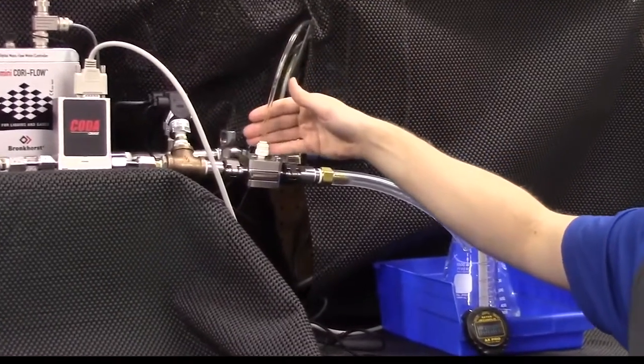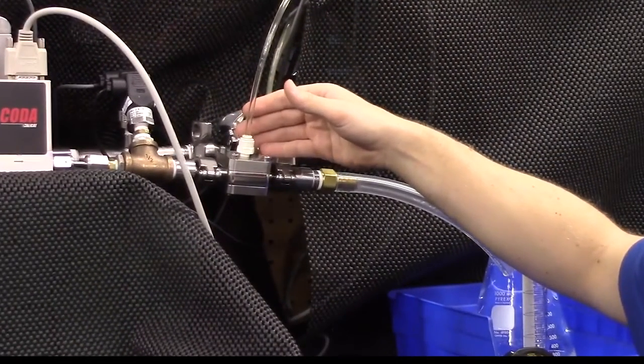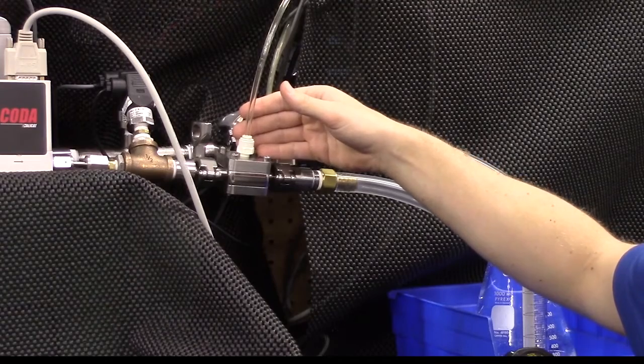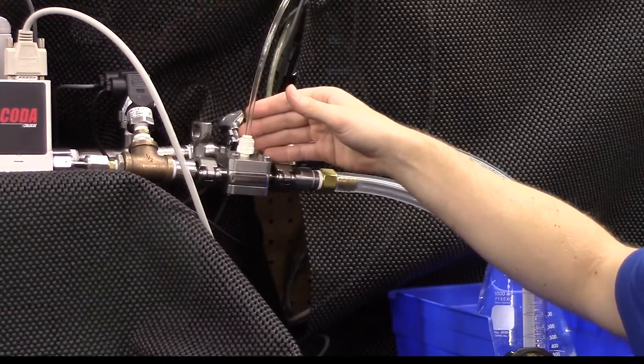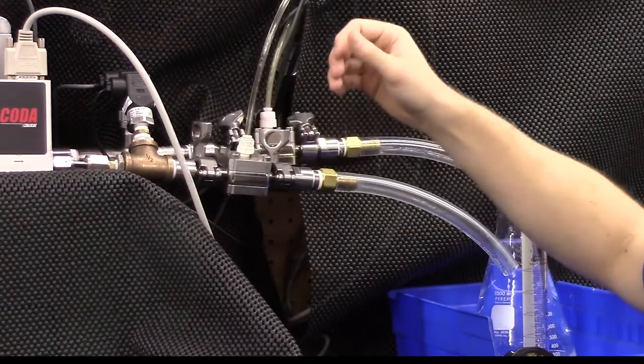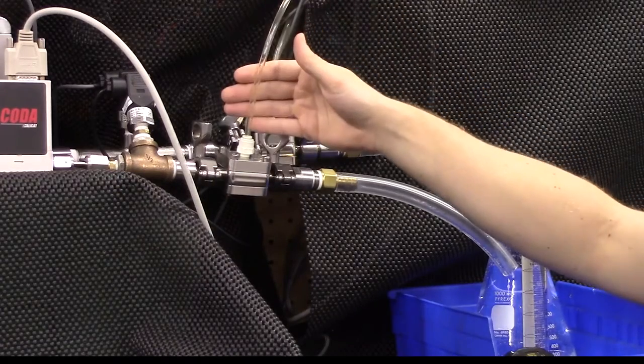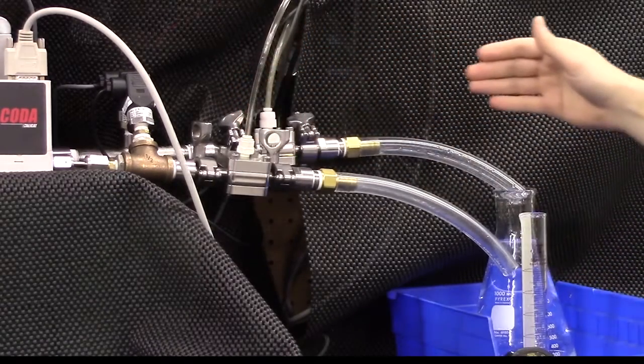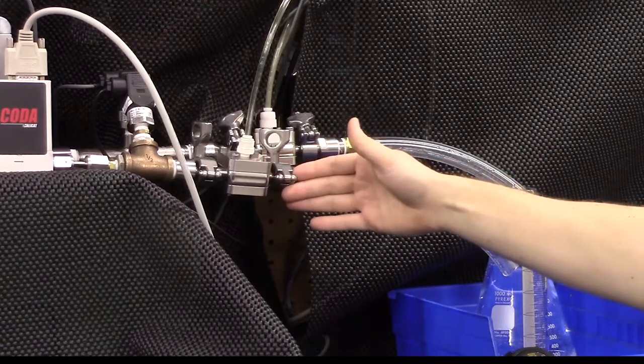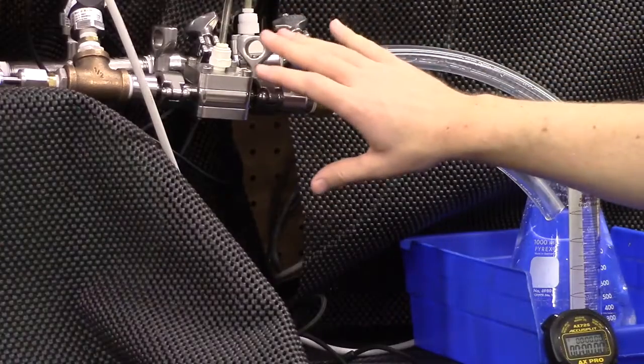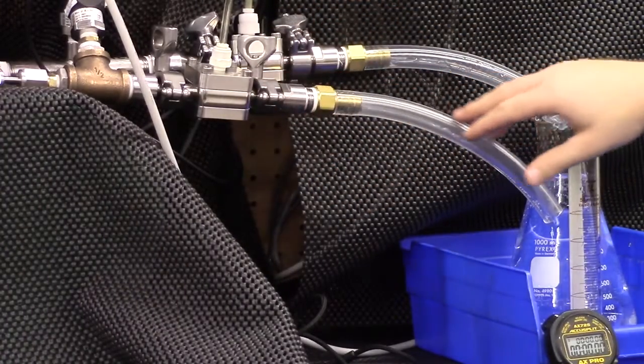that is then interpreting the signal to a pneumatic set point to the BPR. For some additional information on how that works, feel free to take a look at our normal flow control how it works video. We can put a link below for some more information there. This pneumatic set point is then controlled to modulate your flow through the back pressure regulator. From the outlet of the back pressure regulator, it exhausts directly to atmosphere.